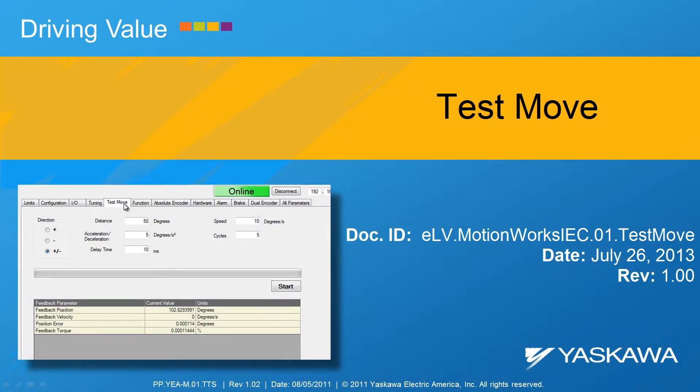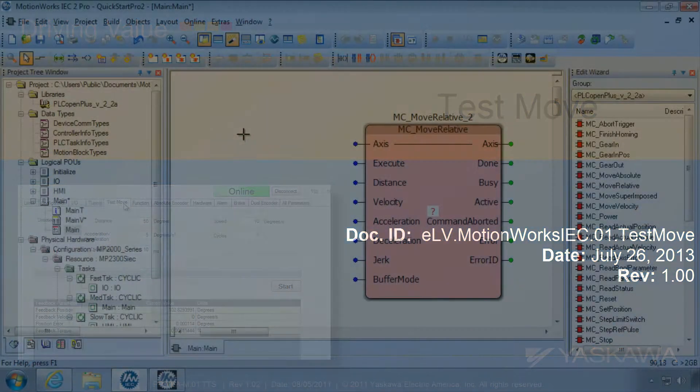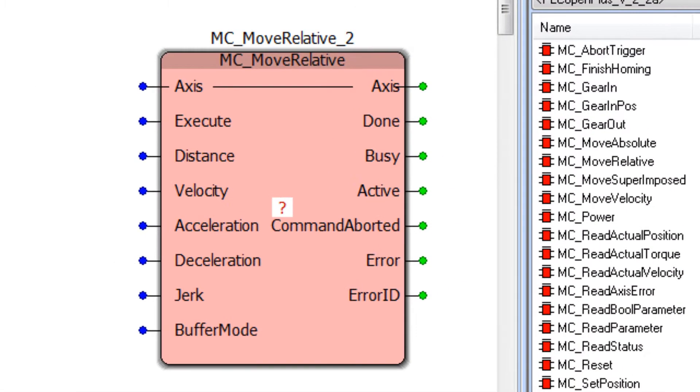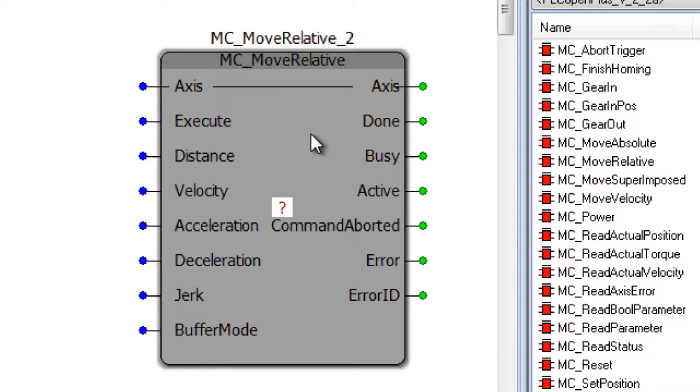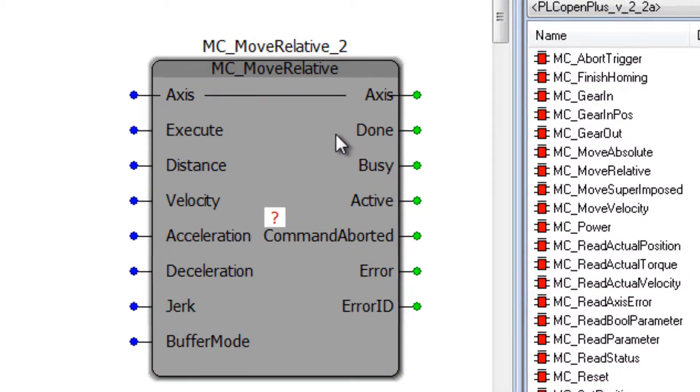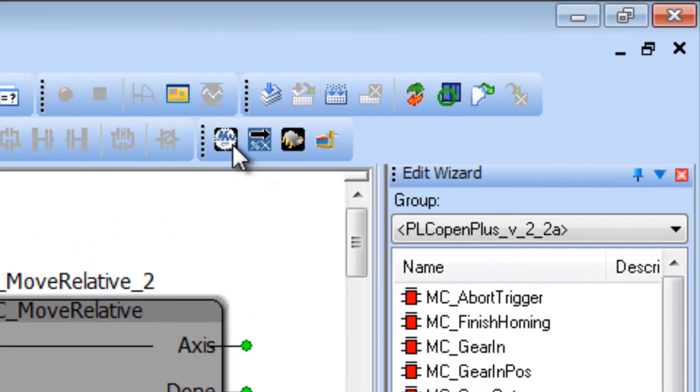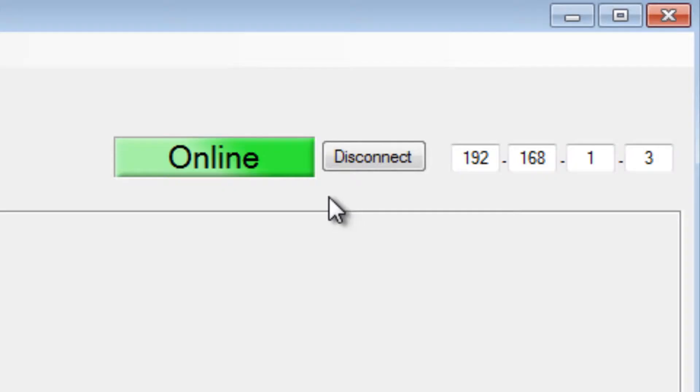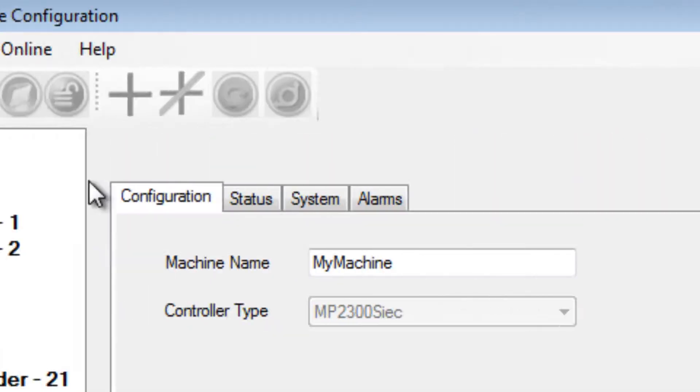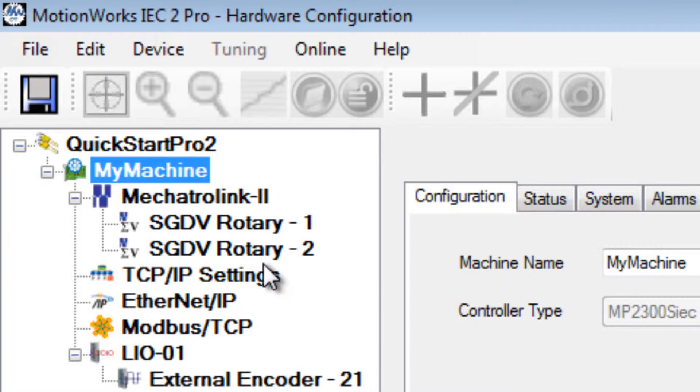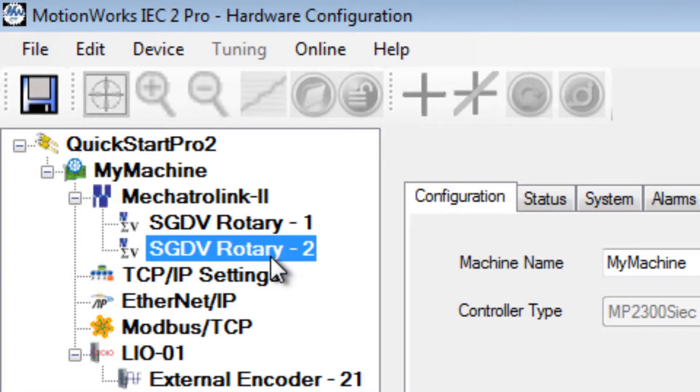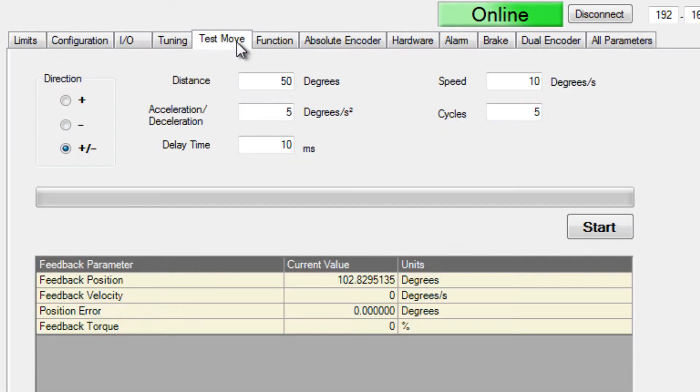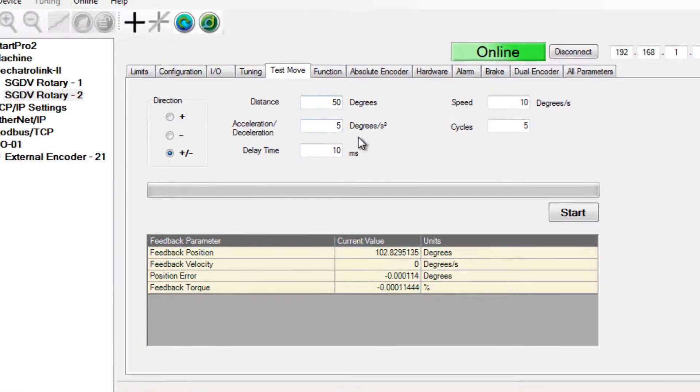This video shows how to run a test move in MotionWorks IEC, followed by a few troubleshooting tips. Before you start programming a block such as MC Move Relative, you can quickly test motion in the hardware configuration. Connected online under each Mechatrolink axis, the test move tab runs the axis according to the configured units.